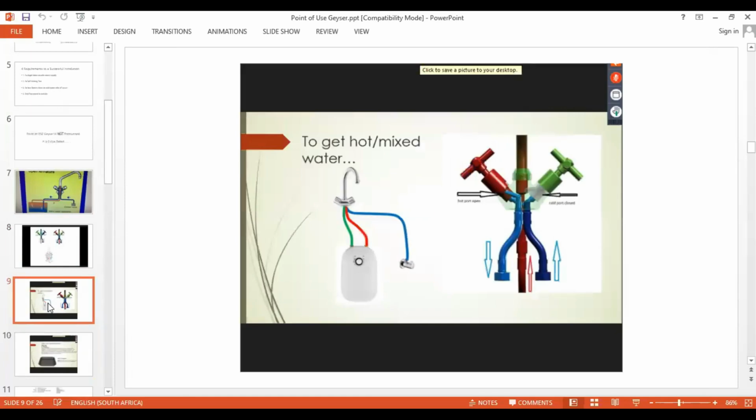So moving on to the next picture, if we have a look here, that is what you have. You have an angle valve. Cold water of the mixer is attached to the angle valve. The hot water is connected to the vessel, which goes through a non-return valve, and the third remaining pipe is connected to the hot water outlet. And that's it. It's as simple as that. You need the self-venting mixer, you need an angle valve, a non-return valve, and a drip tray. It's really as simple and as easy as that.